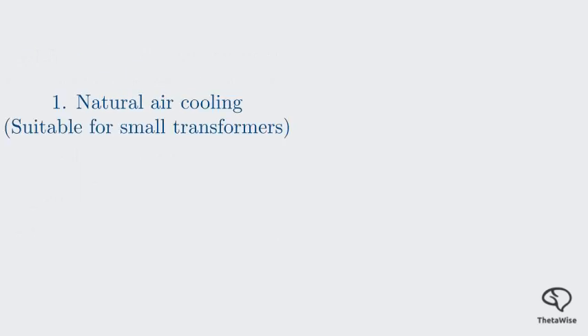Let's start with natural air cooling. This is the simplest method, suitable only for small transformers. As seen in Figure 4.5, there are no fans or pumps. The heat from the windings and core simply radiates into the surrounding air, which then rises and is replaced by cooler air. The process is entirely passive.